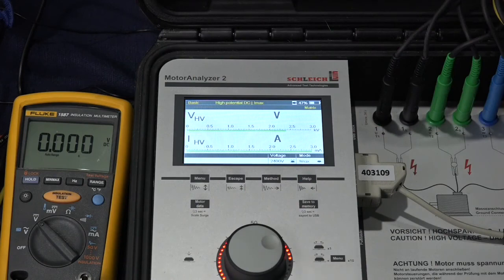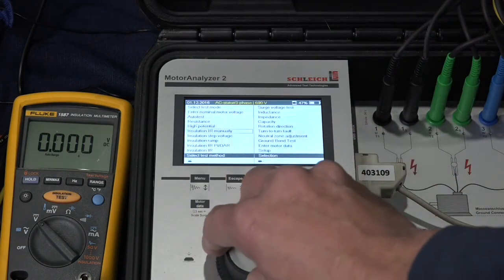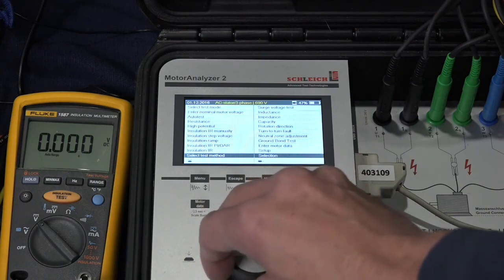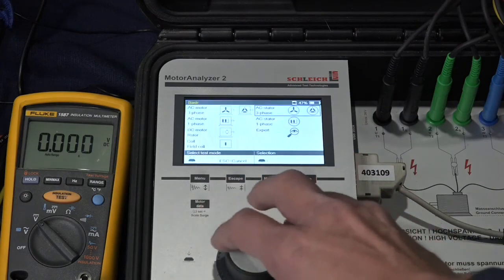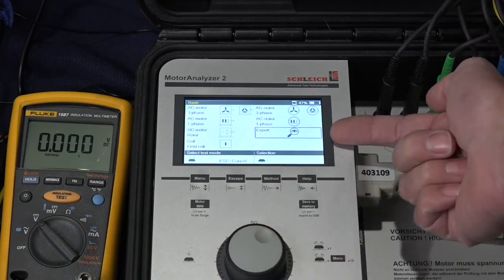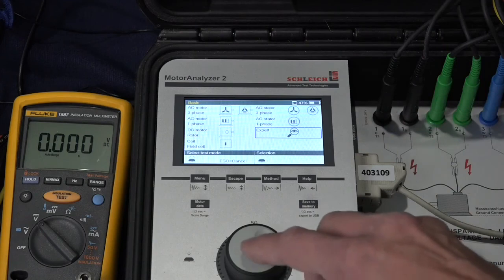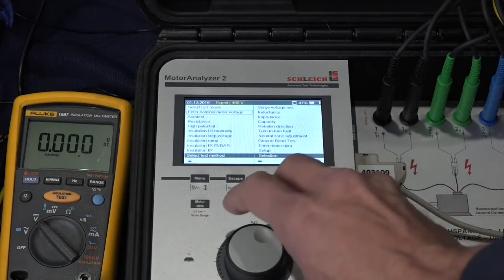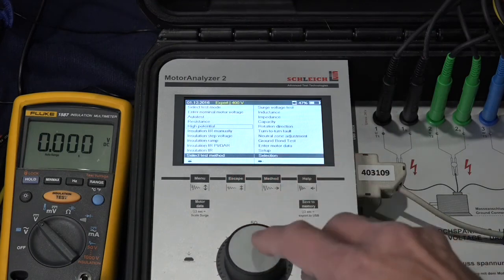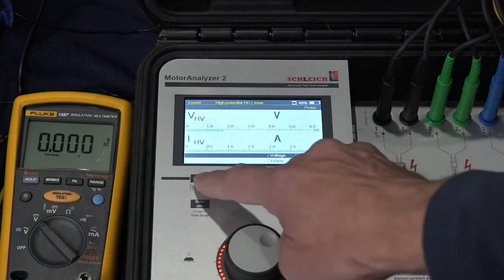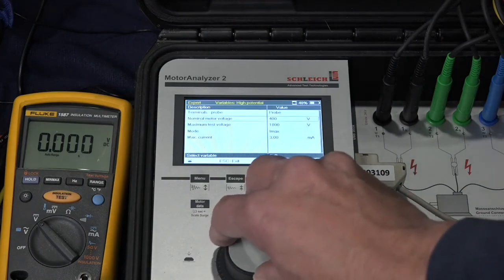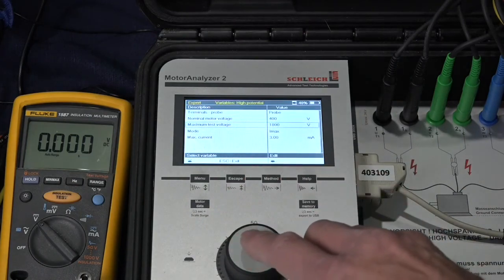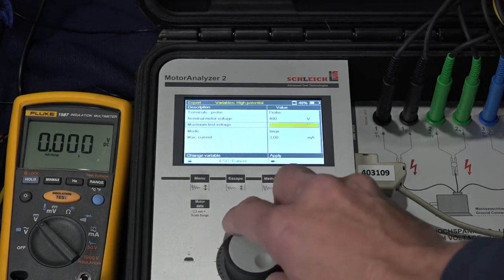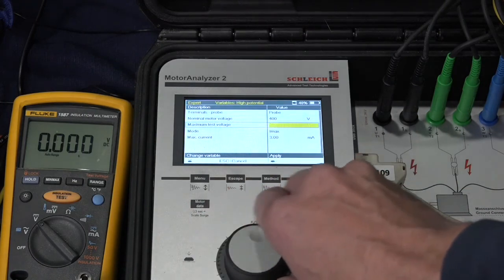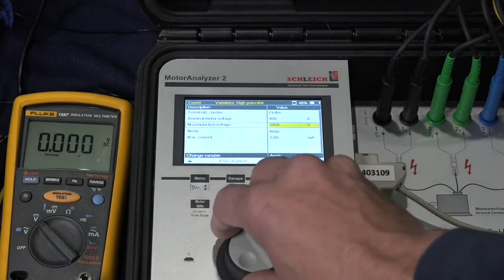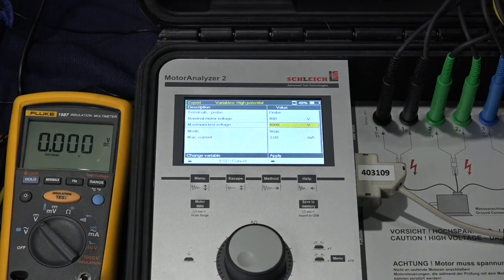There's something called an expert mode. Let's look at that. In the expert mode, we can set whatever voltage we want on the test leads on this high voltage separate lead. So on the right hand side here, you can see there's an expert mode option. Let's select that. Once we're there, we can come down to the high potential test, press the menu item, and notice here we can select the maximum test voltage we want to go to. Let's set it high. Let's go nuts here. Let's go to 4 kV. I think this little stator will handle that, but let's find out.